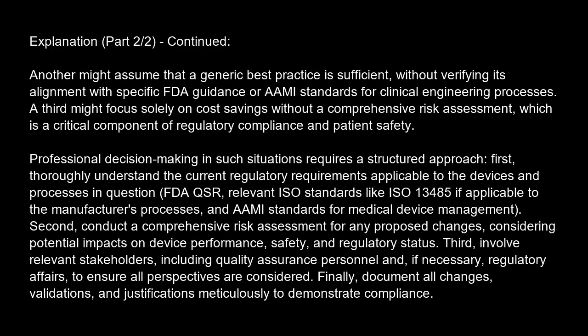Second, conduct a comprehensive risk assessment for any proposed changes, considering potential impacts on device performance, safety, and regulatory status. Third, involve relevant stakeholders, including quality assurance personnel and, if necessary, regulatory affairs, to ensure all perspectives are considered. Finally, document all changes, validations, and justifications meticulously to demonstrate compliance.